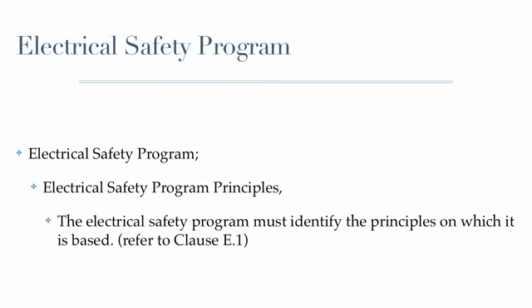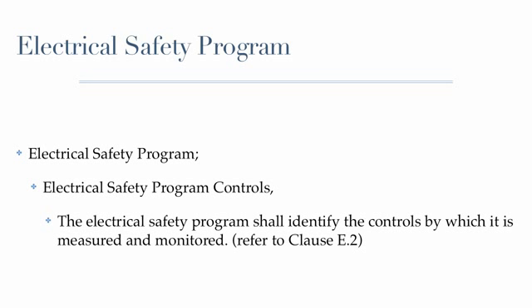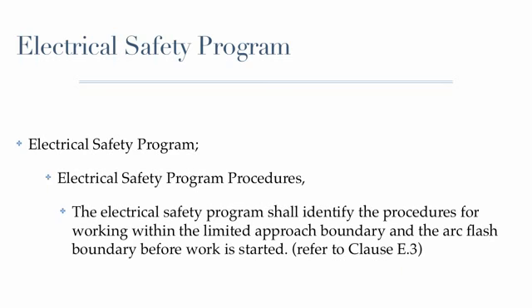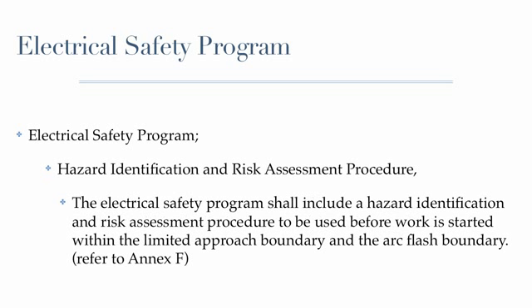The electrical safety program must identify the principles on which the program is based. The electrical safety program must identify the controls by which the program is measured and monitored. The electrical safety program shall identify the procedures for working within the limited approach boundary and the arc flash boundary before work is even started. The electrical safety program shall include a hazard identification and risk assessment procedure to be used before work is started.